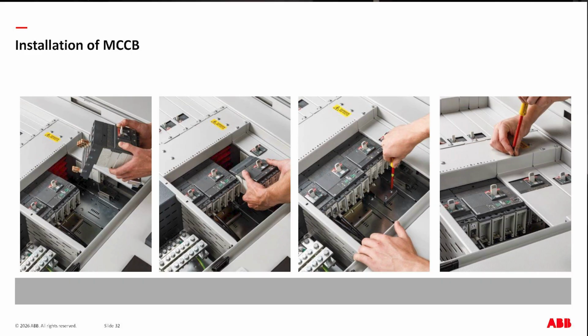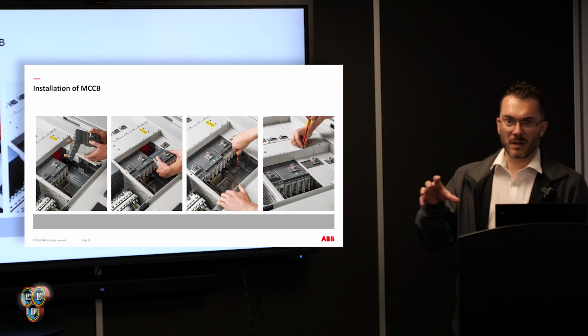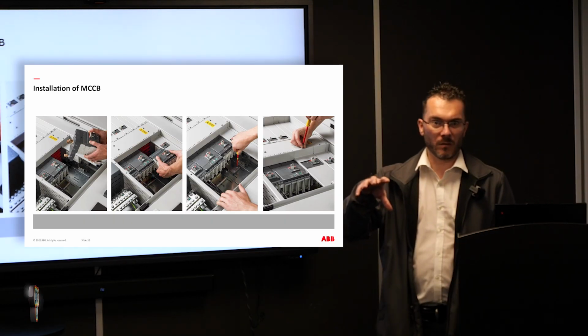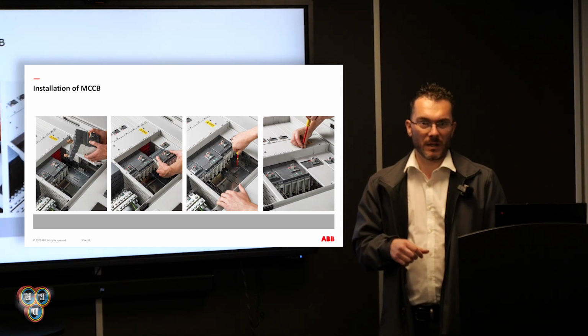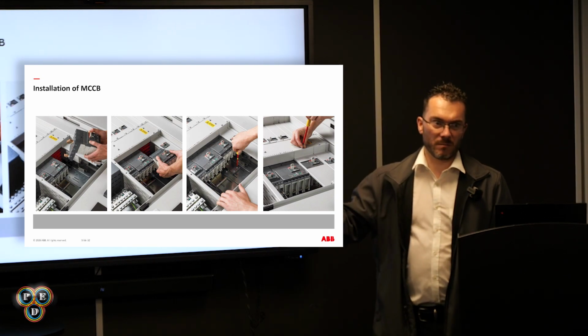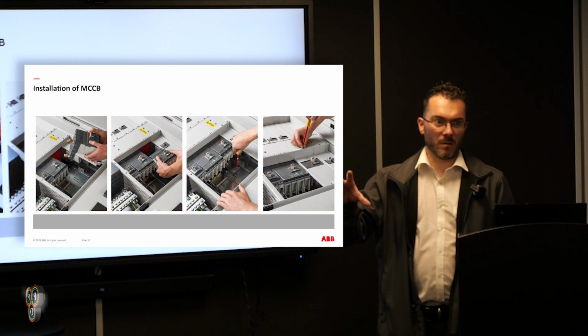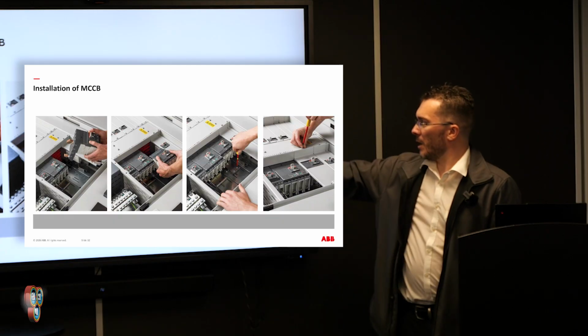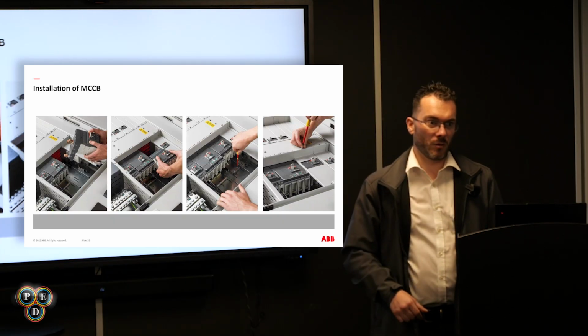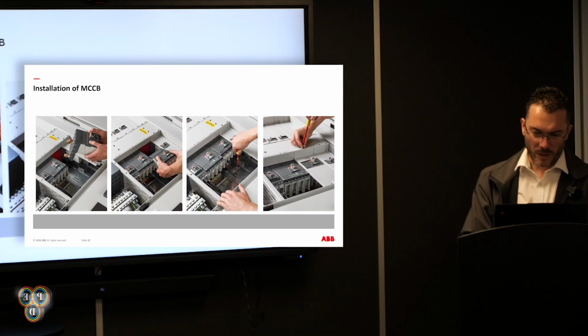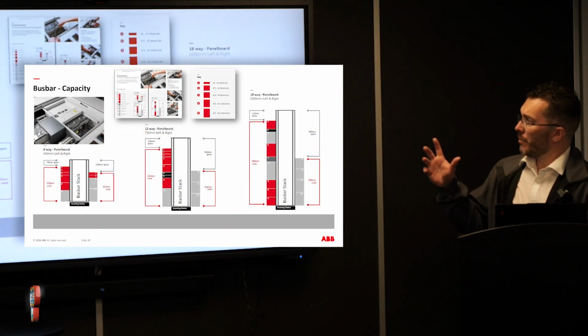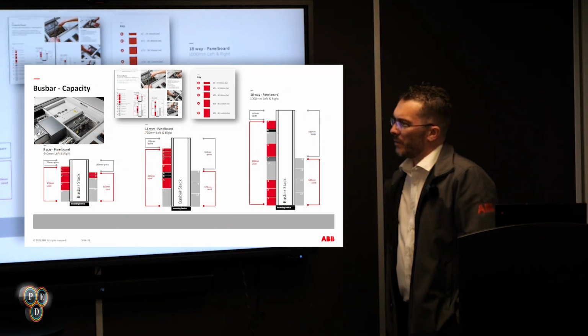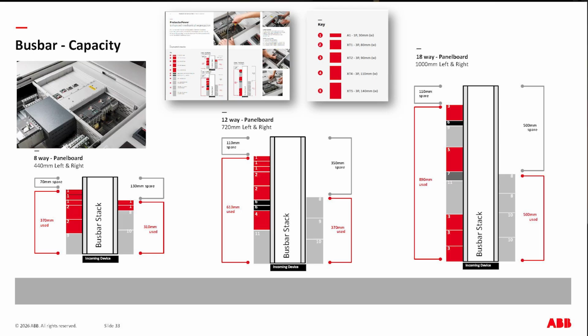Just some examples of fitting the actual devices. The old boards you used to have plug-in bases. You obviously have to slot the MCCB over and then tighten up to required torque settings. There's not that anymore. You literally slot the device in. It will slot onto the busbar and you just tighten up the screws in the mounting plate. A lot quicker installation.